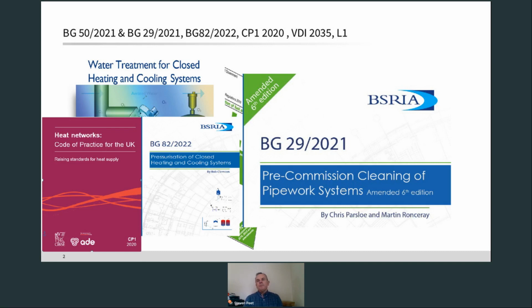Since it's really impossible to directly examine internal surfaces post-clean, the success of pre-commission cleaning is usually inferred from water samples analysed across a range of parameters, including suspended solids, iron and bacteria levels. It also suggests that water treatment comprises a number of techniques, including side stream filtration, degassing and dosing.